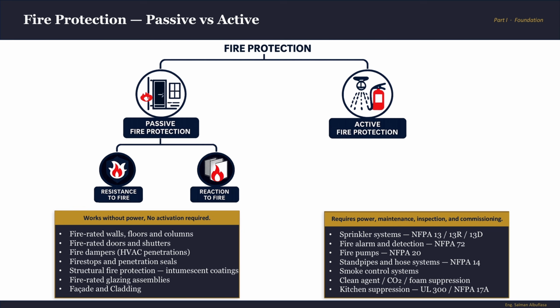It's the intervention layer. The sprinklers, fire alarms, fire pumps, standpipe systems, smoke control, clean agents, and kitchen suppression systems detect fire, suppress it, alert occupants, and manage the smoke environment. And the main thing is, both are always needed. Always. A building with perfect sprinklers but untested firewalls is not a safe building. And a building with beautiful fire-rated construction but no detection or suppression system is equally incomplete.